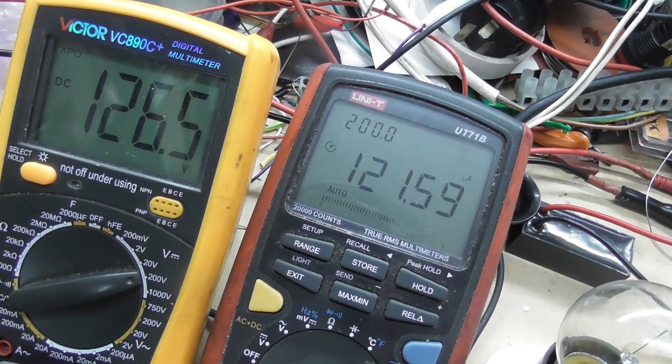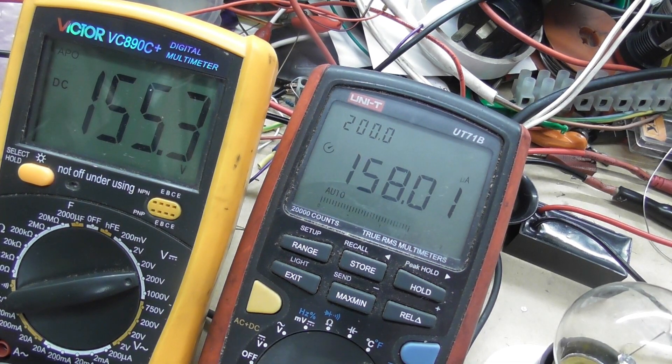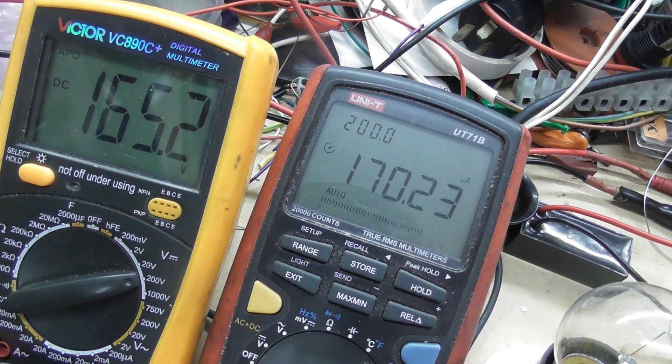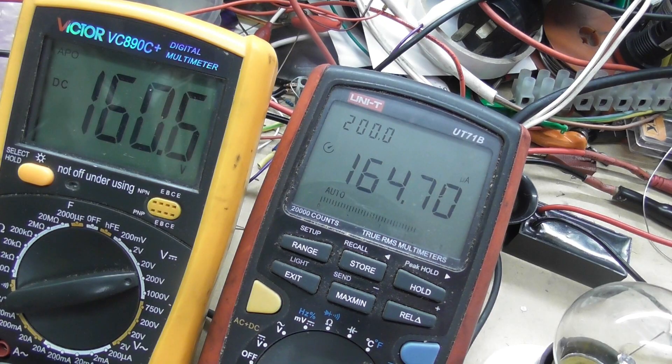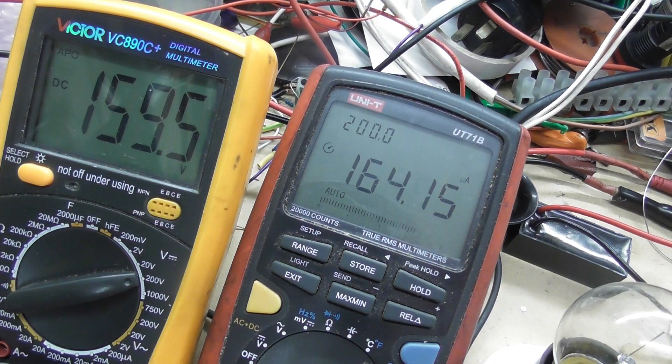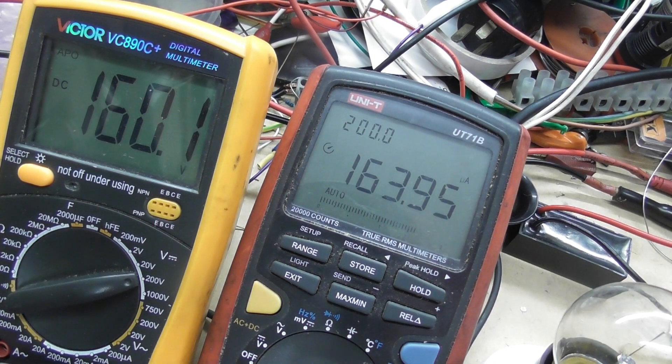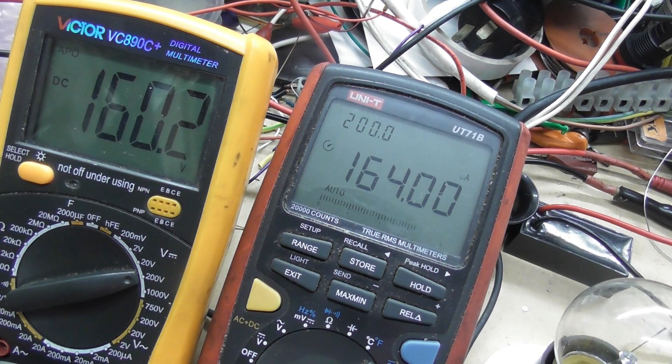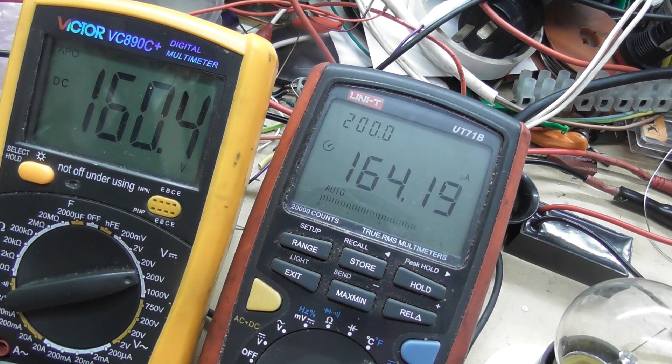I'm going to ramp it up to 160 to see what the reading is there. So 160 volts, 163 microampere. So that device, the SEL, is still in the specs.